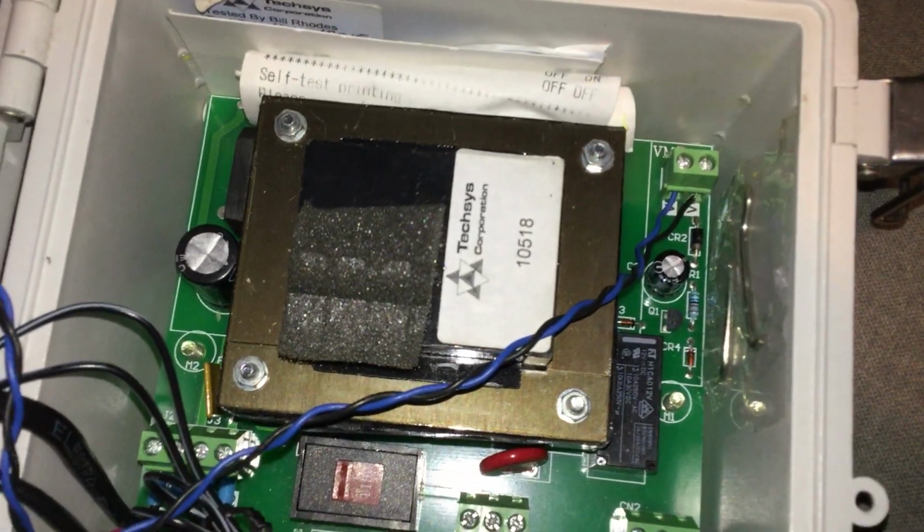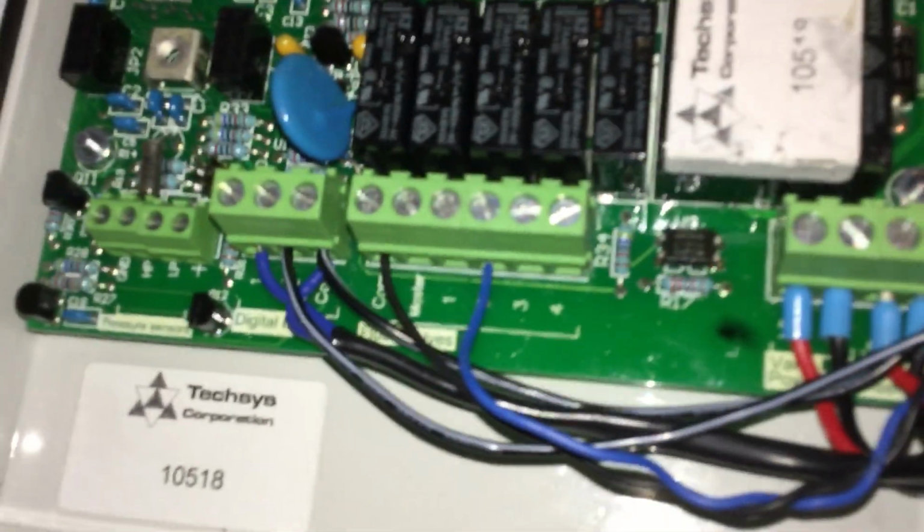So first off, here's a transformer, AC transformer. It has an extra relay in here in case. Every output over here, which I'll show you in a moment, is 24 volts AC, so it's meant for a filter valve. If you need a dry contact relay output, you can wire those 2 terminals up to the output.